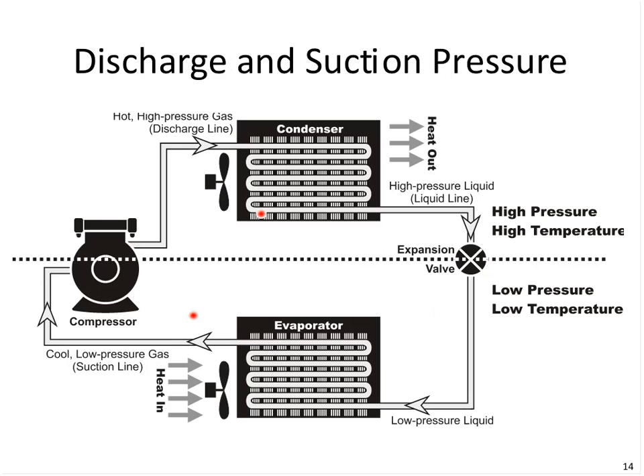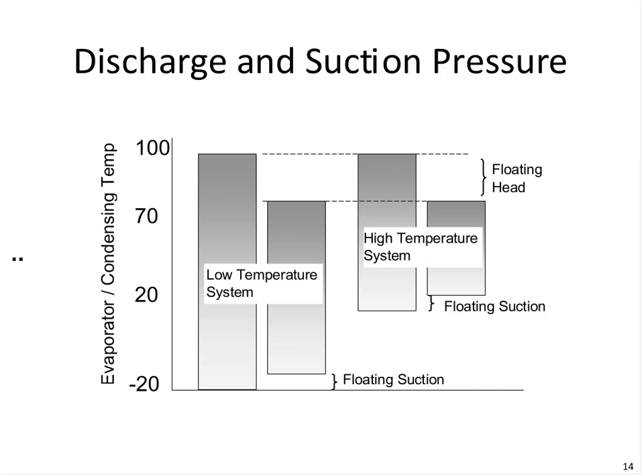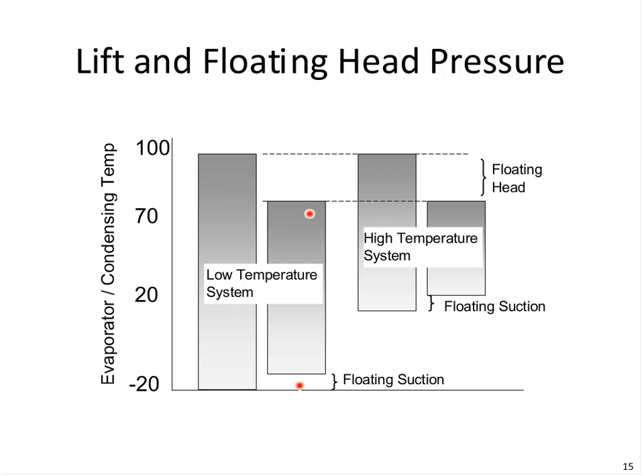And then, of course, on this side of the system, where we're rejecting the heat, if the ambient conditions, be it the humidity or the temperature, are low, we can get the refrigerant condensed at lower temperature and pressure. That's going to give us an efficiency improvement in the area of about 2% per degree. So for every degree we can condense at a lower temperature, we save 2% at the compressor, and for every degree we can get the cooling done at a higher temperature, that also has about a 2% savings per degree. So we call that floating the head or floating the suction.